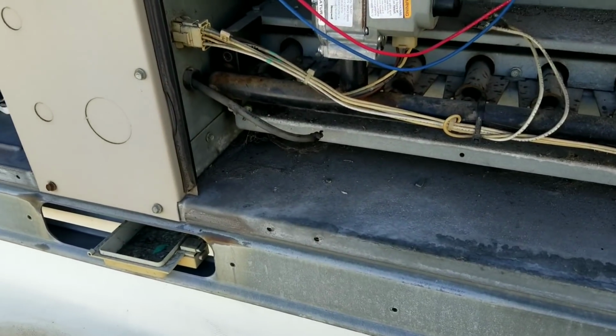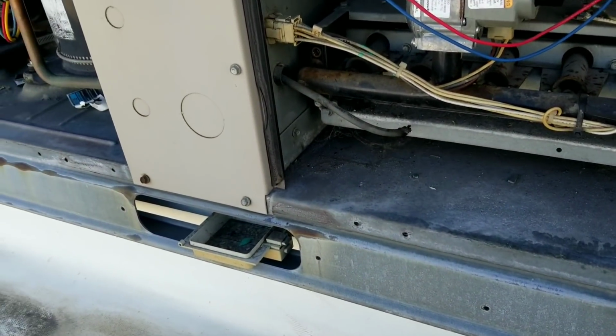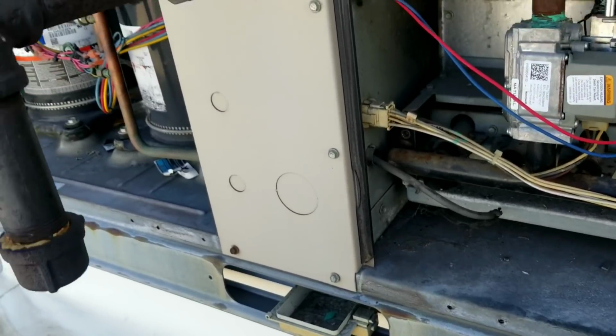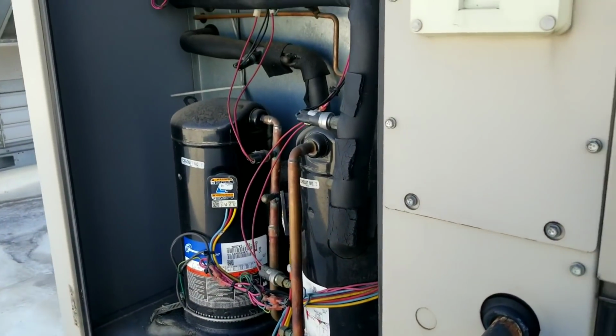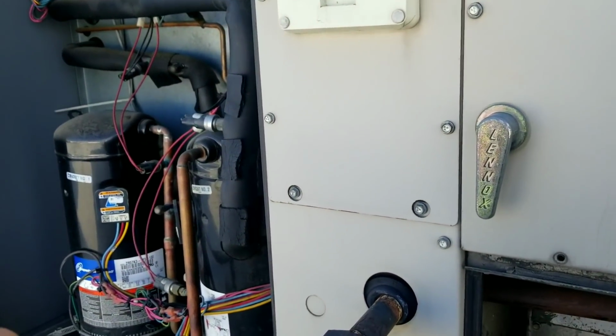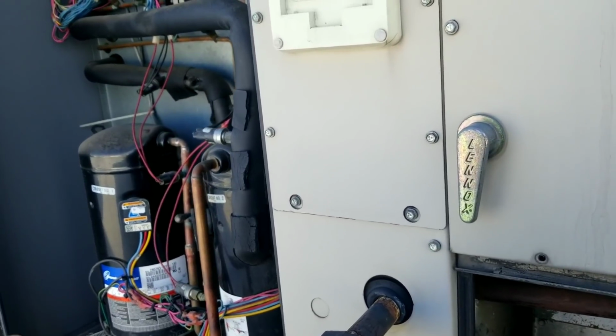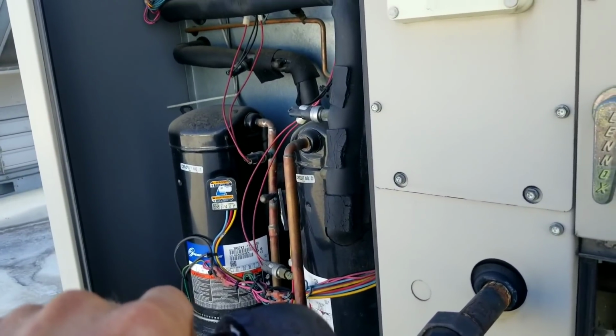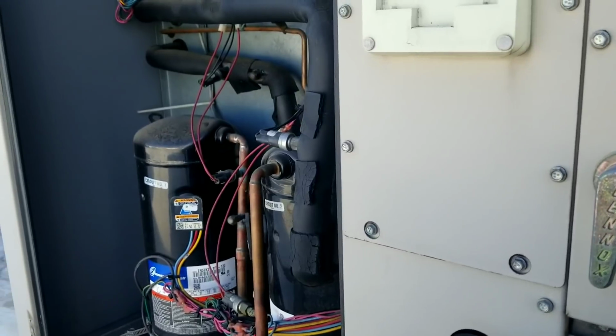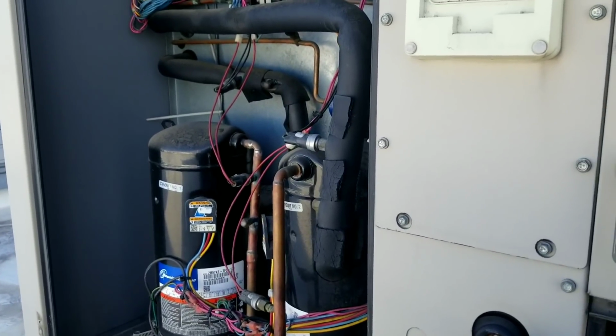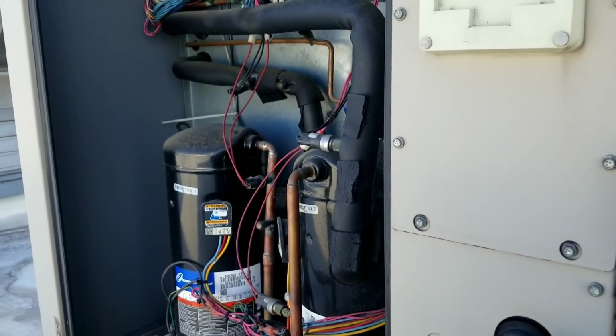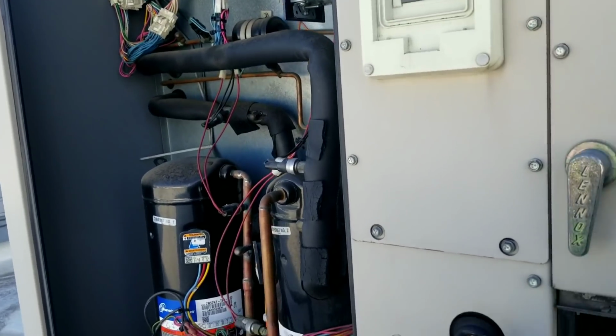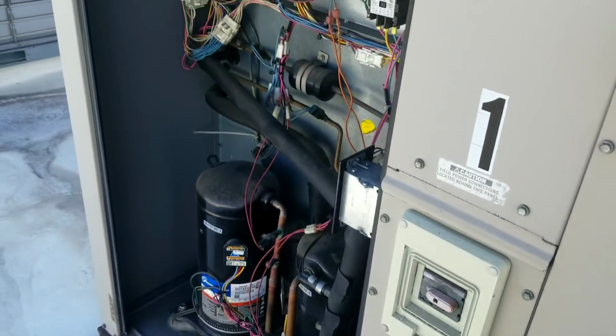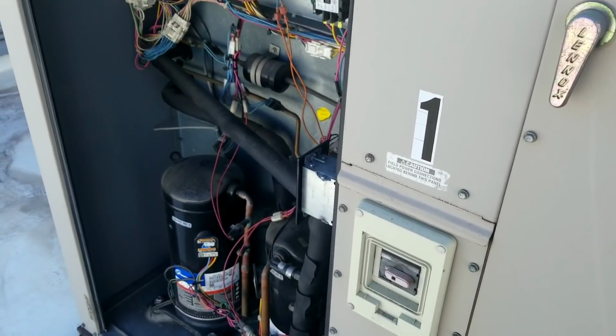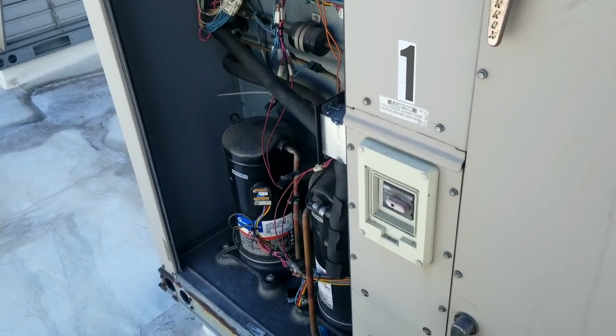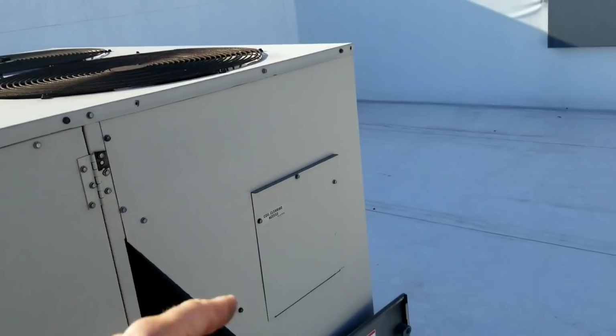So this is where I've kind of started to develop these always things, and I'm sure you guys do it too. For example, if you do a compressor, you always do the contactor, and depending on the layout of the machine, I almost always do condensing motors too. I don't install brand new compressors with old, aging, slow-moving condensing motors - it makes no sense. For an extra $200-300, if I can ensure the brand new compressor lasts longer with a brand new condensing motor, I'll do it.